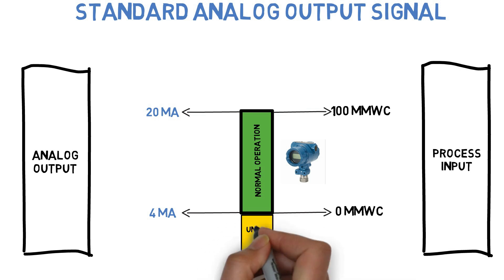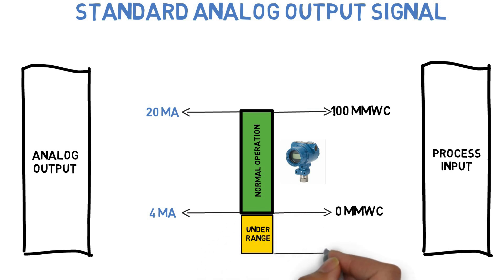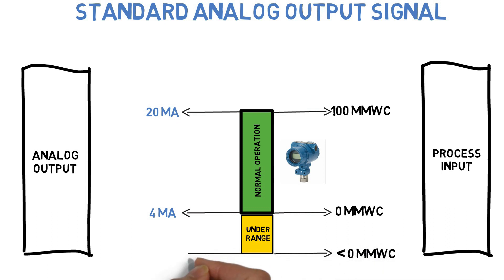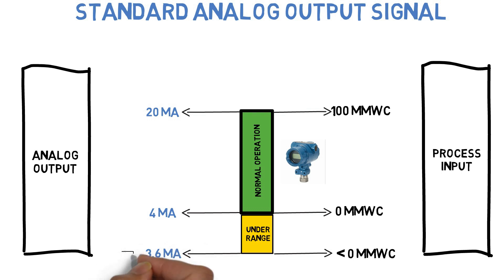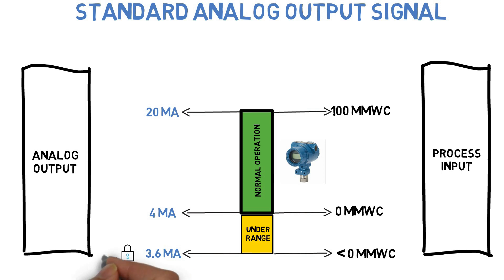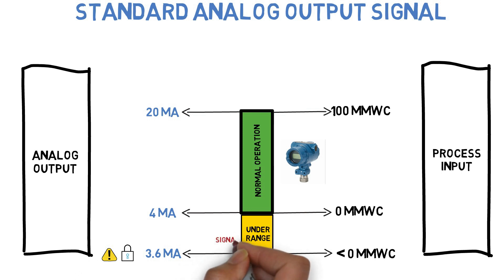If the process input falls below the lower range value of the transmitter, the analog output also reduces between 4 and 3.6 mA. If the process input exceeds the lower range value, the analog output holds at 3.6 mA. Holding at these values warns the control unit of an out-of-range event. This out-of-range signal is referred to as Signal Saturation.